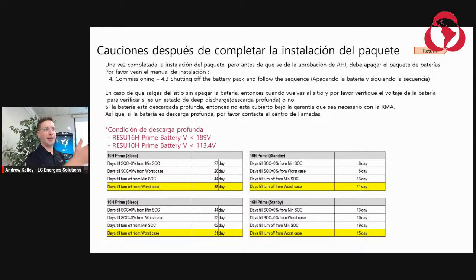When you guys install your systems, do you have to shut everything off and wait a number of days? I'm getting a no — so you can just turn it on and leave it on? Okay, so you don't really have to worry about this. In other parts of the country, you typically install your system and then shut it down for a couple of weeks while you wait for the utility to approve it, then turn it back on. Some people will just shut the inverter off and leave. That could be a problem because the battery is still on, and eventually, after 62 days, it might be completely dead.